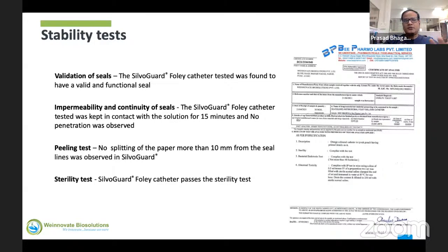Usually there are two types of stability testing. One is real time: if you are giving an expiry of 3 years, you have to keep the catheters for 3 years and check what is happening to them. The other is accelerated aging. There is the Arrhenius formula, which relates temperature and the shelf life you are promoting. If you feed that formula with the details, it will tell you for how many days you need to keep the device at a particular temperature to get stability for 3 years. In our studies, we have done accelerated aging, and in that we have checked the validation of seals, because the seal is very important. If the seal is broken, the sterility of the catheter is compromised and it is of no use. The other thing we have done is impermeability and continuity of seals.